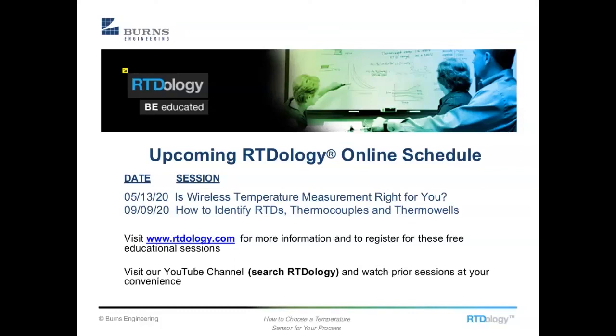In our experience, if you do some basic maintenance checks on your sensors, you do some calibration, and you pay attention to what's happening over time, that's a better predictor than trying to put something in place, because there are so many conditions and it can only monitor so many. But there are some out there, and a little bit of an additional fail-safe helps to alert you in case you're not doing regular maintenance or calibration of your sensors.